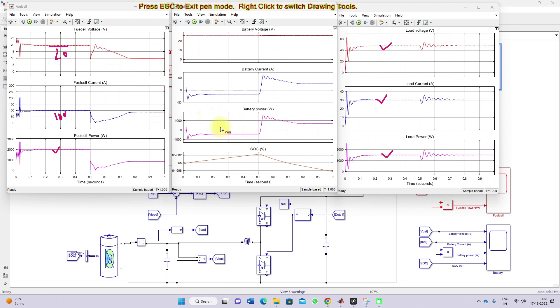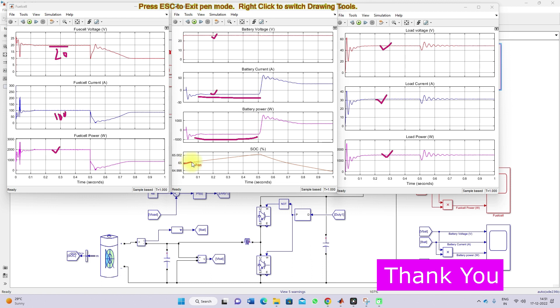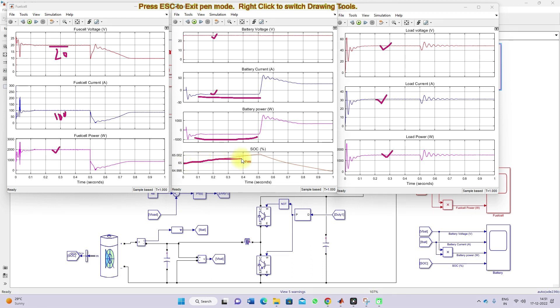The remaining power is used to charge the battery. You can see the battery voltage and battery current — the battery current here is negative, which means the battery is in charging mode. The battery power is also negative, confirming the battery charging mode. The SOC of the battery is increasing from 65 percent in a rising manner, confirming that the battery is in charging mode from 0 to 0.5 seconds.